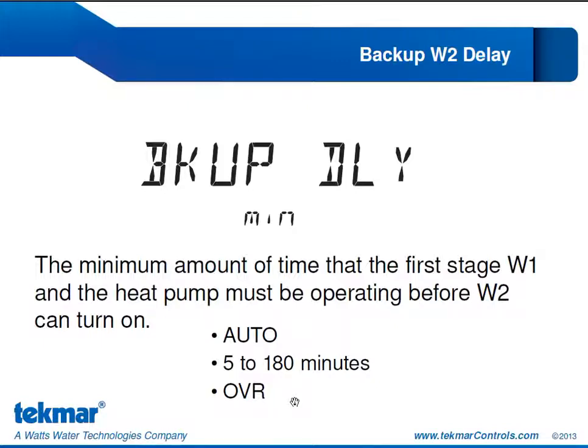Now, the backup delay is not used if we are in emergency mode. In emergency mode, only W1 and W2 operate. So we're not going to enforce an additional delay on W2 when we only have W1 and W2. We'll bring W2 on as needed.